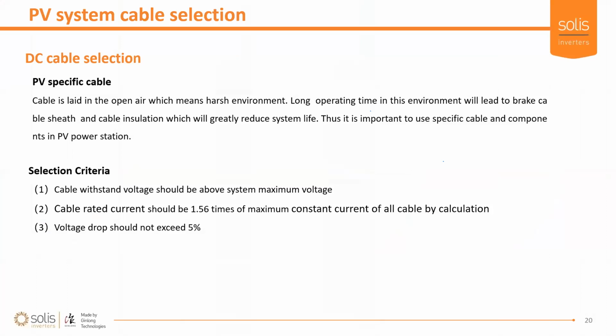Generally, your DC or PV cables run outside or on top of the roof, therefore hit by bad weather conditions. A good insulation that is designed for this should be considered, and maybe, if possible, trunking would be a good idea, especially running through a building. The main three things to consider when designing your PV cables: the insulation must be able to handle the voltage on the cables.